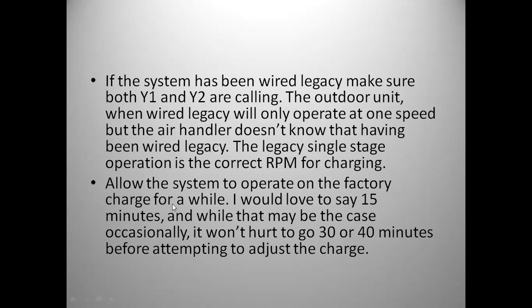Do allow the system to operate on factory charge for a while. Do not start making a whole bunch of adjustments. Now, a caveat to that is if you're in a downflow position and you have a short line set and you started up your factory charge, you may indeed be overcharged right out of the box. So if you notice your pressures are skyrocketing, then you'll want to recover some refrigerant to get to a stable level, so you're not going to start hitting high pressure. Once these are in charge mode, allow them to stabilize. They say 15 minutes to be stable.